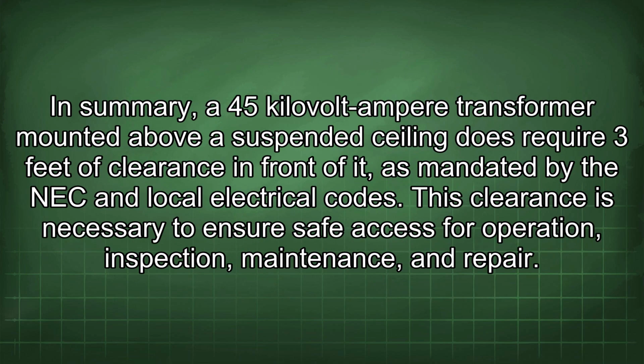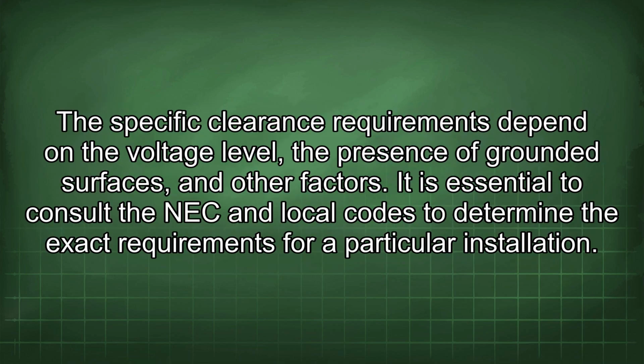In summary, a 45 kilovolt-ampere transformer mounted above a suspended ceiling does require 3 feet of clearance in front of it, as mandated by the NEC and local electrical codes. This clearance is necessary to ensure safe access for operation, inspection, maintenance, and repair. The specific clearance requirements depend on the voltage level, the presence of grounded surfaces, and other factors. It is essential to consult the NEC and local codes to determine the exact requirements for a particular installation.